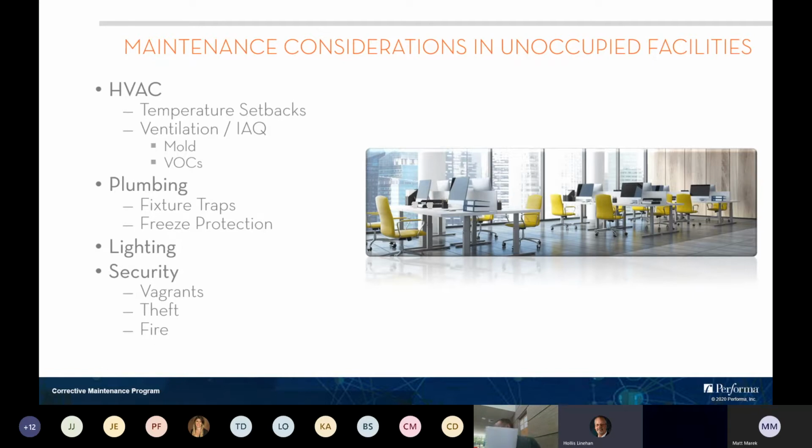There's also, if we go in and start resetting our temperatures in the summertime so that the interior spaces get a little warmer, if we decide we're going to save energy and reset our temperatures to 85 degrees, some of the newer, not the brand new, but the newer optical switches, they can only handle temperatures of about 100 degrees. And so those pieces of equipment can be very expensive, and sitting in a data closet with a temperature reset, they can actually be damaged and actually fail with an excessive temperature.